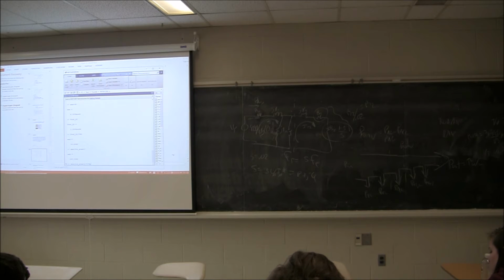That's my S. Now I'm going to divide that by P out. This is the actual. Does everybody understand what I'm doing here? I'm doing the actual output, not just what I'm assuming is the nameplate. So now it's 2.57 kVA per horsepower.